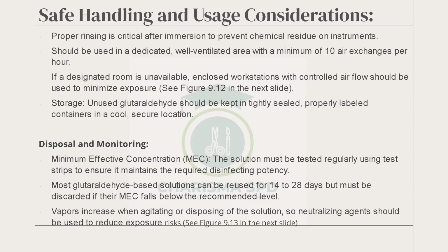So you must rinse it to make sure that all the residual films of the chemical are washed away. Otherwise, some will be left on the instrument, and we don't want that. Now, ventilation, 10 air exchanges per hour. The decontamination room and the prep and pack both have 10 air exchanges per hour. The sterile storage has 4 air exchanges per hour. But high-level disinfection is not done in the storage area. Never done. Storage is storage. So high-level disinfection has its own.